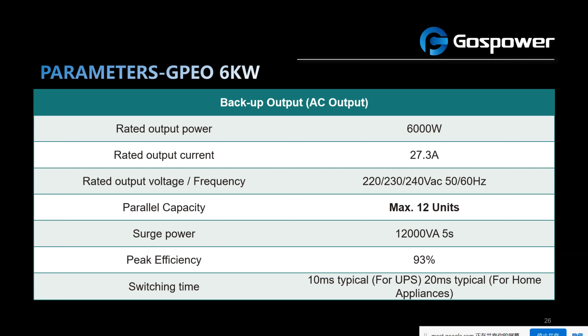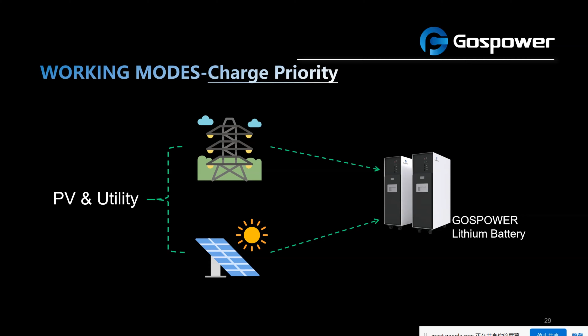The last page is about the working modes of the inverter. Our inverter mainly has 3 charging modes. The first one is PV priority, which means the system will use power from the solar panels to charge the lithium battery first. If the solar energy is not sufficient, the inverter will use the utility to charge the lithium battery. The second is PV and utility mode, where the solar panels and utility charge the lithium battery at the same time. The third mode is PV only charging.